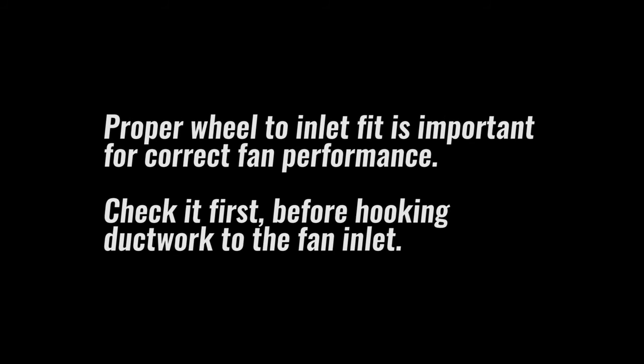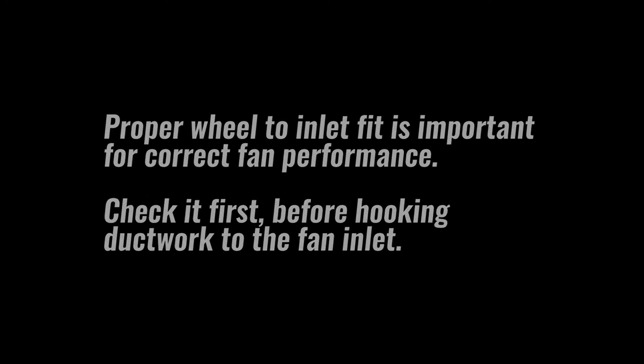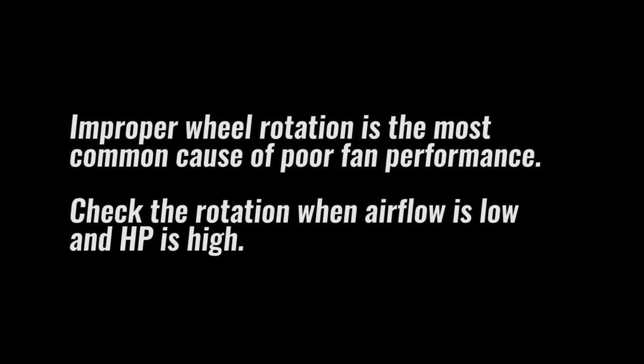Okay, let's recap. Proper wheel to inlet fit is important for correct fan performance. Check it first before hooking ductwork to the fan inlet. Improper wheel rotation is the most common cause of poor fan performance. Check the rotation when airflow is low and horsepower is high.